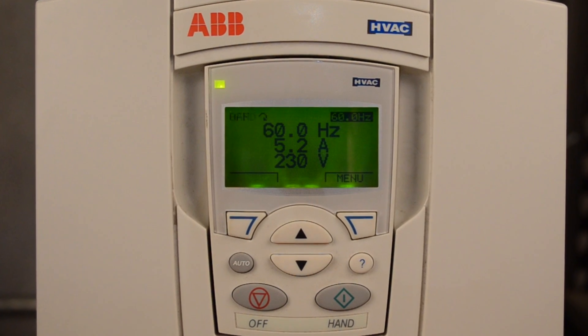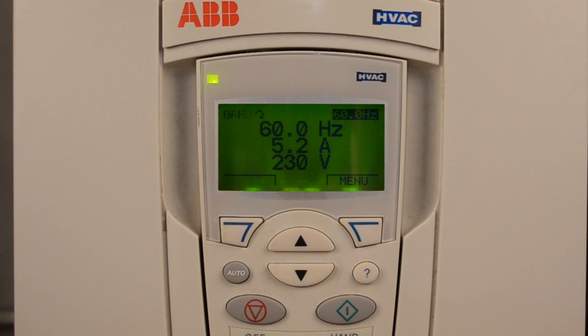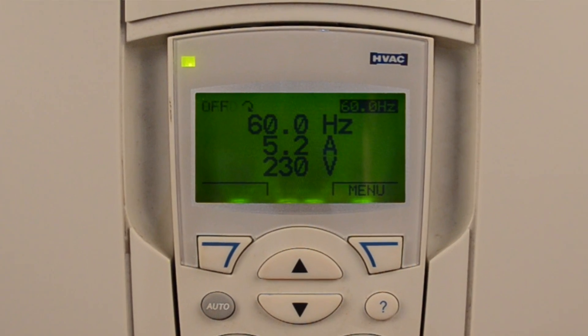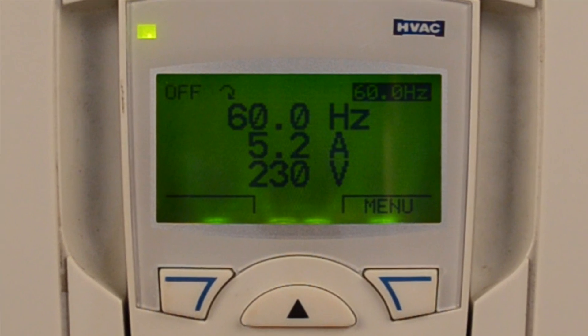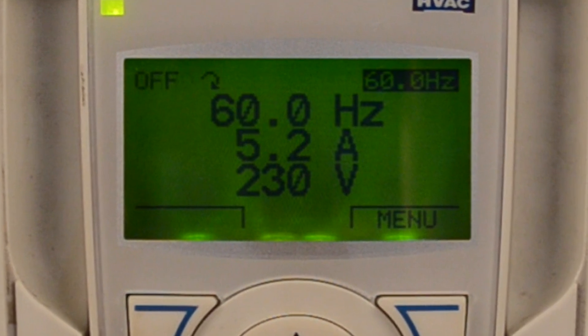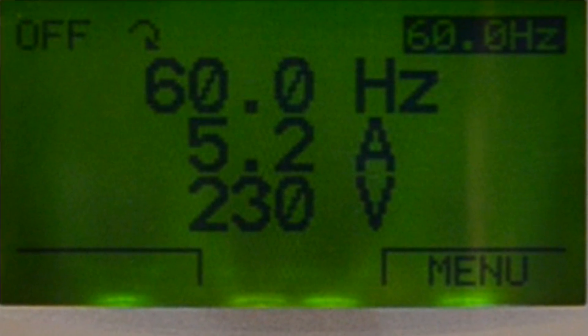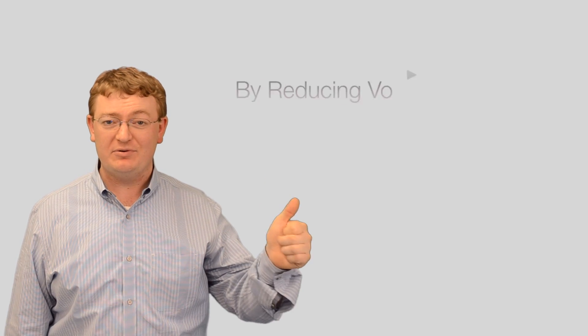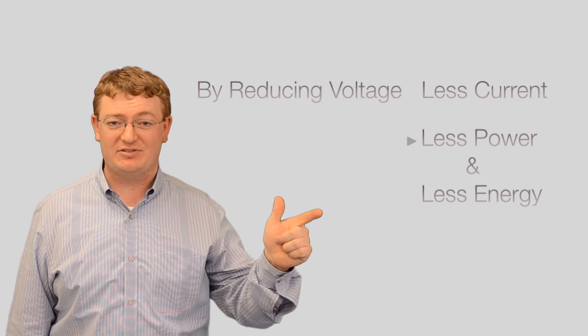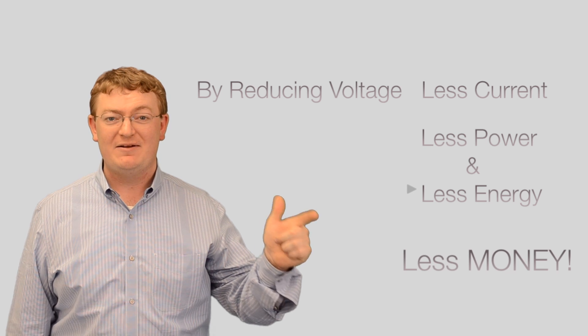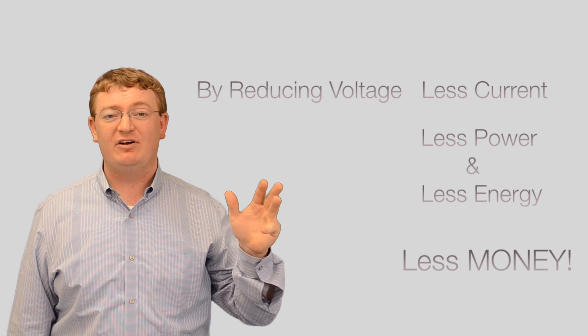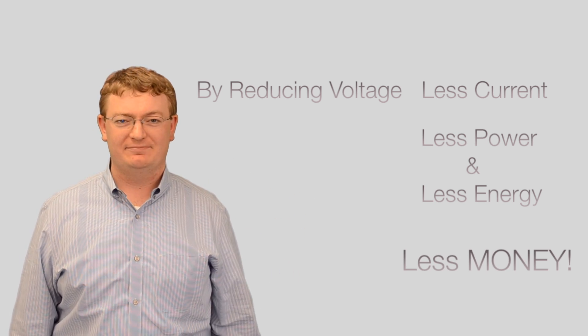It is not uncommon to see on a 460V motor and system that the VFD is running at 60Hz, but the voltage is less than 300V. By reducing both the voltage and the current going to the motor, we have reduced the kilowatts going to that motor — the power, the energy, and above all, the money spent on that motor.